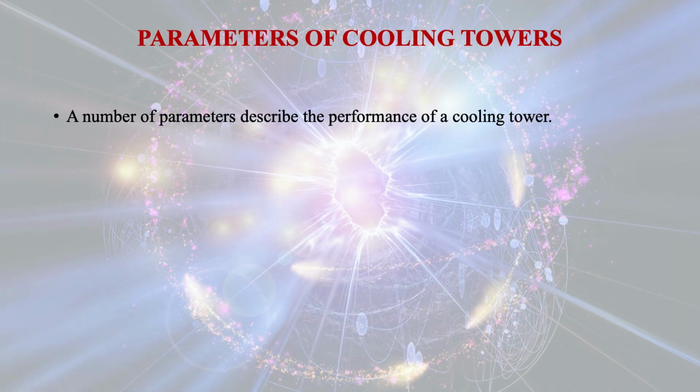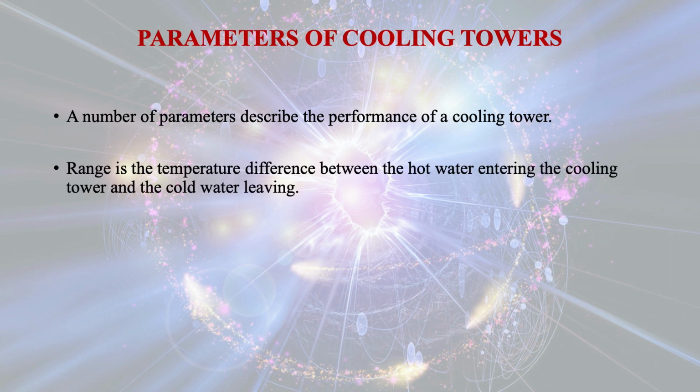Now let us discuss about the parameters of cooling tower. A number of parameters describe the performance of a cooling tower. Range is the temperature difference between the hot water entering the cooling tower and the cold water leaving. The range is virtually identical with the condenser rise.